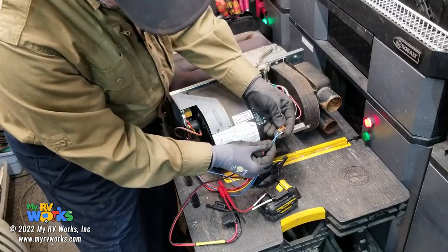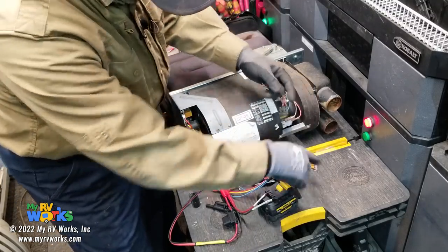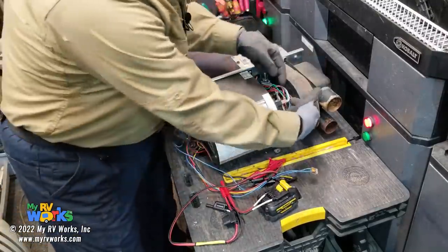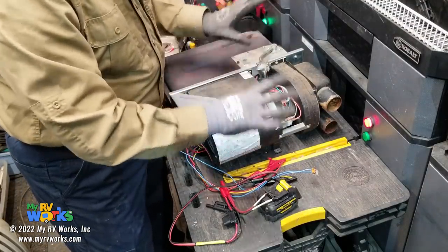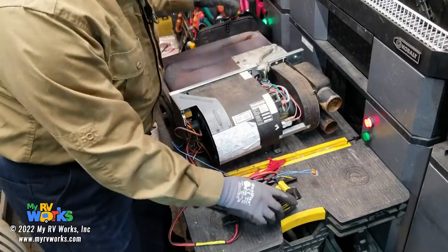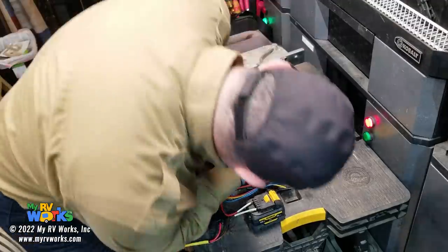And I'm going to connect this to become the thermostat, call for heat. So now I've got a call for heat. So we've got 12 volts coming up, 12 volts going back, going through here. I'm coming into here. This relay is an on delay, off delay. So he's kind of been told to turn on, but he's going to, there he goes. Okay. So now we're happy and healthy. Our gas is on. And our sail switch is made.